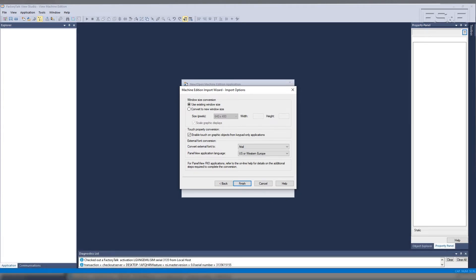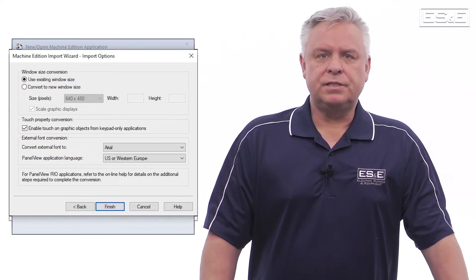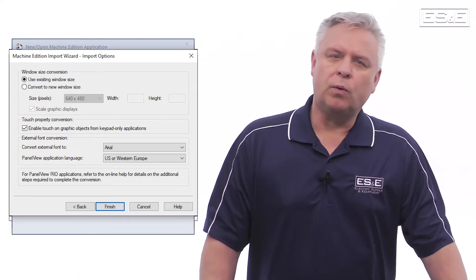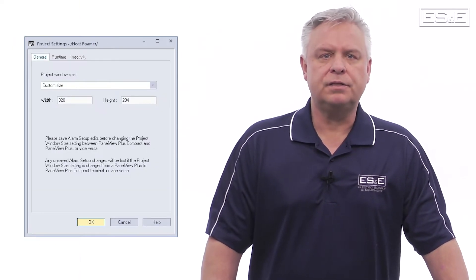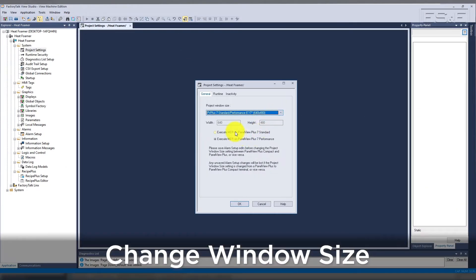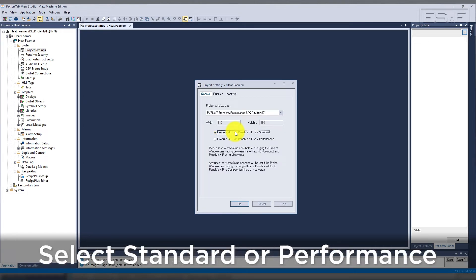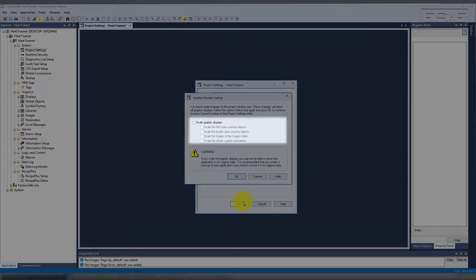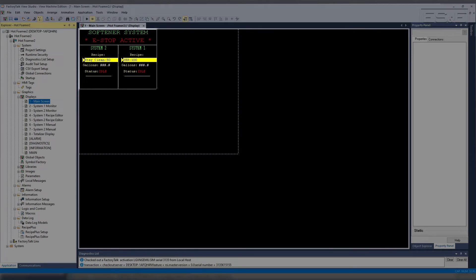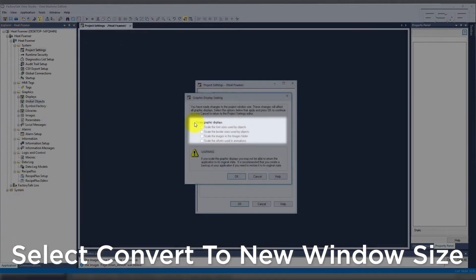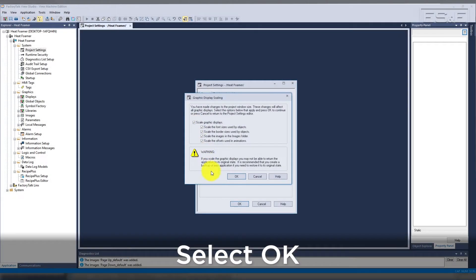We're going to stay at a high level, but I do want to point out two things. If you select 'Use Existing Window Size,' then it will use the resolution of the Panel Builder 32 file. Once the import is complete, go into Project Settings and look at the original resolution. Change the window size from the custom size to the resolution of the new Panel View Plus 7 and select either Standard or Performance, then select OK. If 'Scale Graphic Displays' is deselected, the application will only take up a fractional area of the screen. If you are converting to a Panel View Plus 7 with higher resolution than the original application, select 'Convert to New Window Size' and leave 'Scale Graphic Displays' checked, then select Finish.